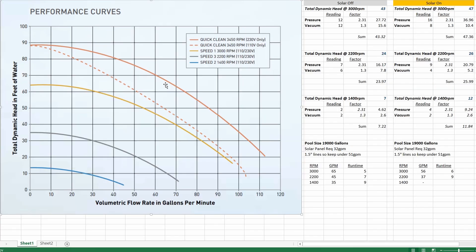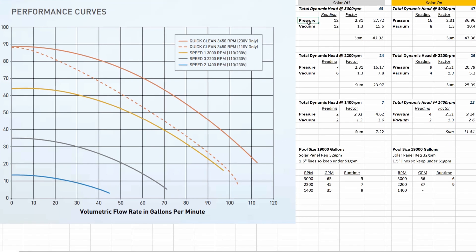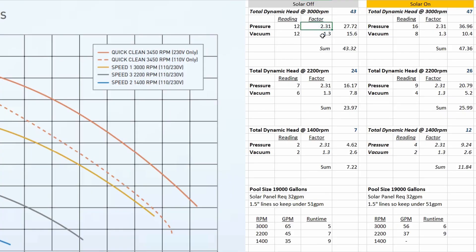So to get my gallons per minute I just need to figure out my total dynamic head using the pressure and vacuum readings I took outside. So on the right side here you can see that I've recorded the various pressure and vacuum readings of the different RPMs that line up with those performance curves on the left here. So all I need to do is multiply these readings by these factors here and then sum the products to get me my total dynamic head at each RPM.